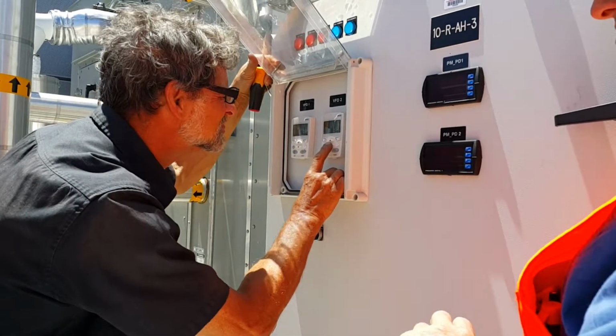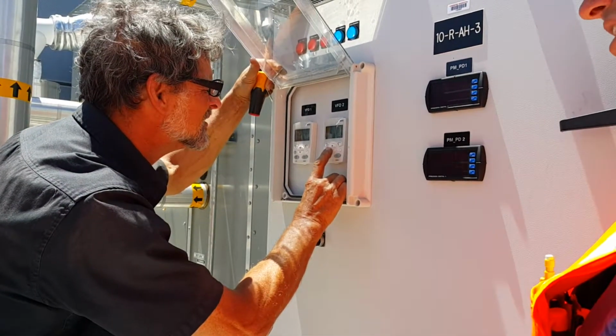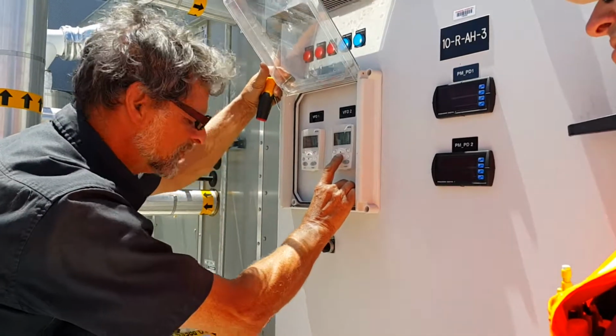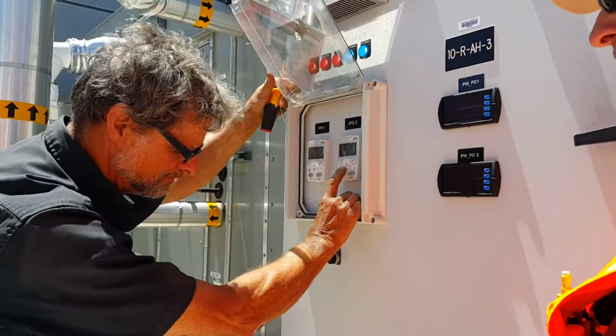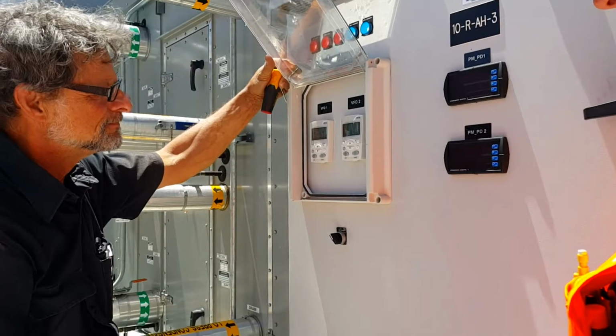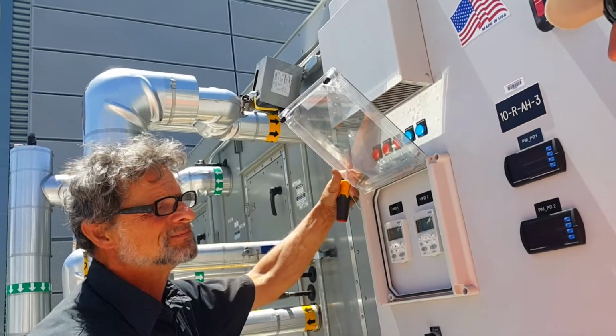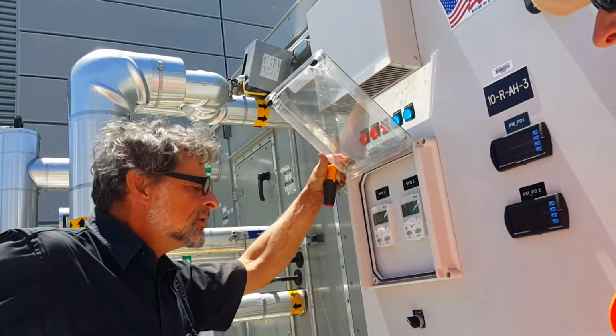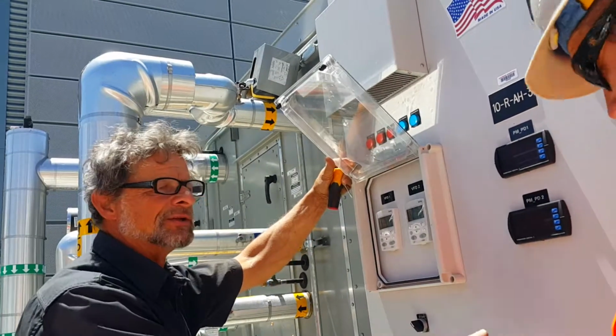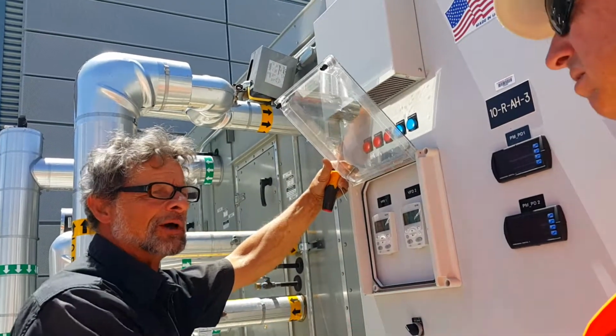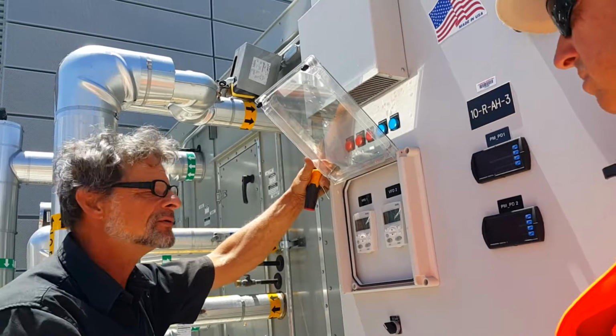It's okay to just turn the switch anytime. You don't have to ramp anything down or anything like that. Do you recommend ramping it down and shutting one off, switching it over, and then bringing the power back on? It's always better to do that. But if you make a mistake and you didn't realize it came up to run and you wanted to switch it over, you can just switch it over.